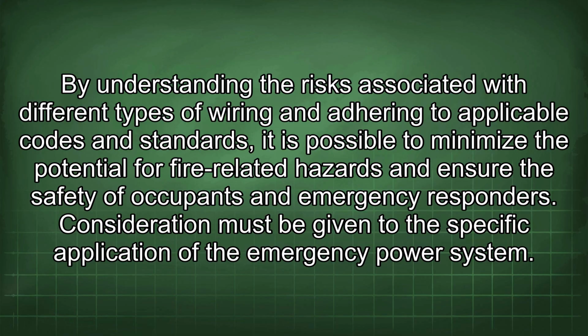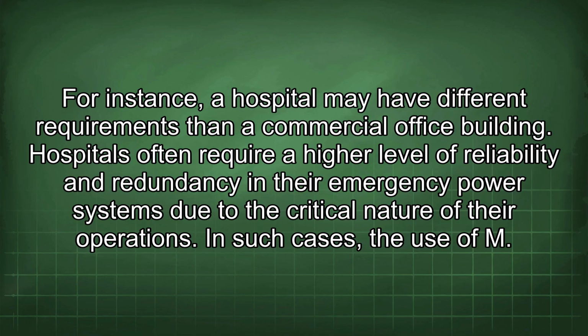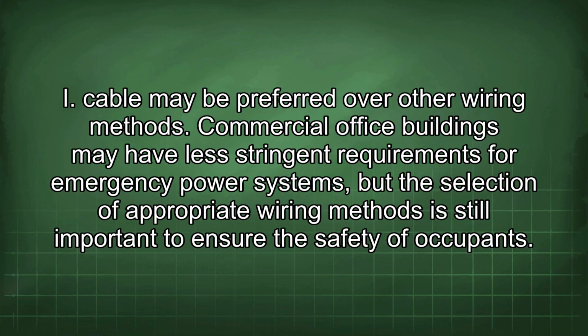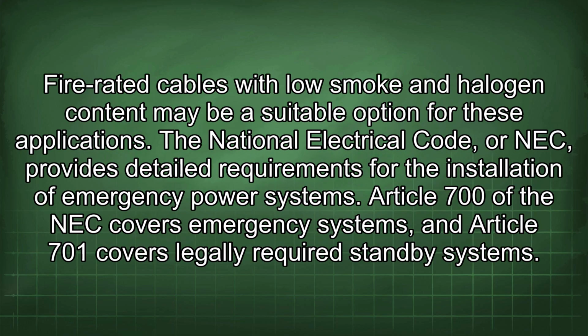Consideration must be given to the specific application of the emergency power system. For instance, a hospital may have different requirements than a commercial office building. Hospitals often require a higher level of reliability and redundancy in their emergency power systems due to the critical nature of their operations. In such cases, the use of MI cable may be preferred over other wiring methods. Commercial office buildings may have less stringent requirements for emergency power systems, but the selection of appropriate wiring methods is still important to ensure the safety of occupants. Fire-rated cables with low smoke and halogen content may be a suitable option for these applications.